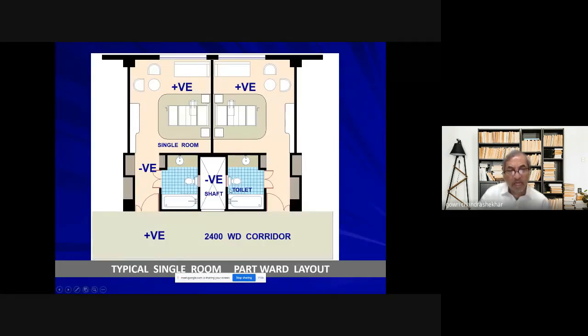The in-between barrier, the lobby, becomes negative; the toilet becomes more negative; and the shaft becomes the highest negative. The shaft can be operated or maintained from the outside corridor in a multi-story building, so we don't have to enter from the toilet area to disturb it, while the room itself stays in positive pressure.